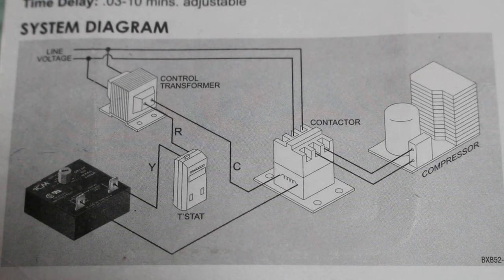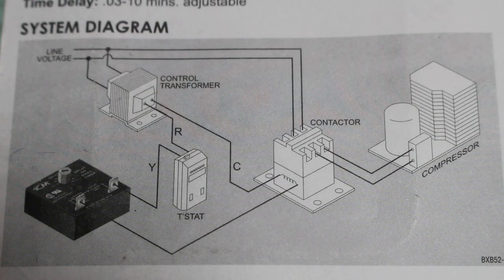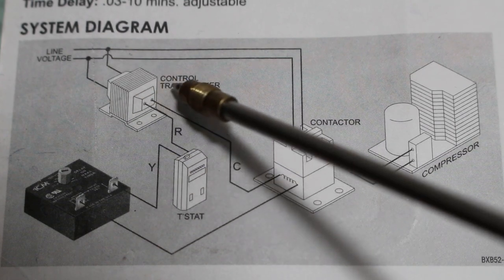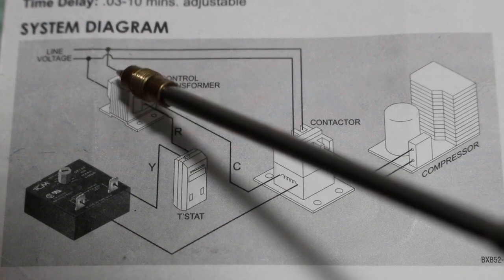Let's start with line voltage coming in here. We have two legs — this is 240 volts single phase. As it comes in, it branches off one leg to our primary for our control transformer, and the second line branches off to our second leg for the primary of our control transformer, with 120 volts in each leg giving us a total of 240 volts.